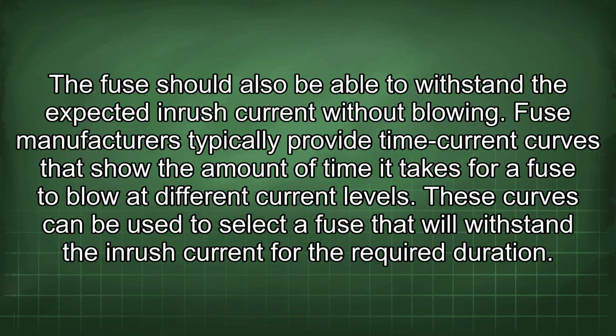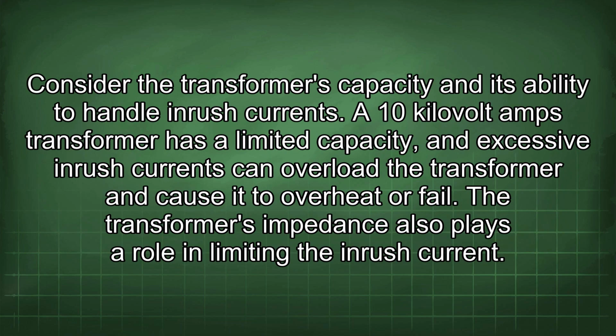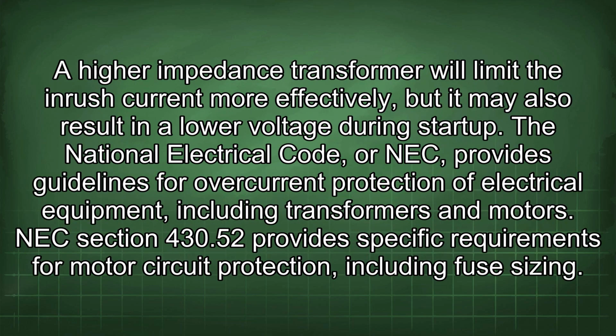Fuse manufacturers typically provide time current curves that show the amount of time it takes for a fuse to blow at different current levels. These curves can be used to select a fuse that will withstand the inrush current for the required duration. Consider the transformer's capacity and its ability to handle inrush currents. A 10 kVA transformer has a limited capacity, and excessive inrush currents can overload the transformer and cause it to overheat or fail. The transformer's impedance also plays a role in limiting the inrush current. A higher impedance transformer will limit the inrush current more effectively, but it may also result in a lower voltage during startup.